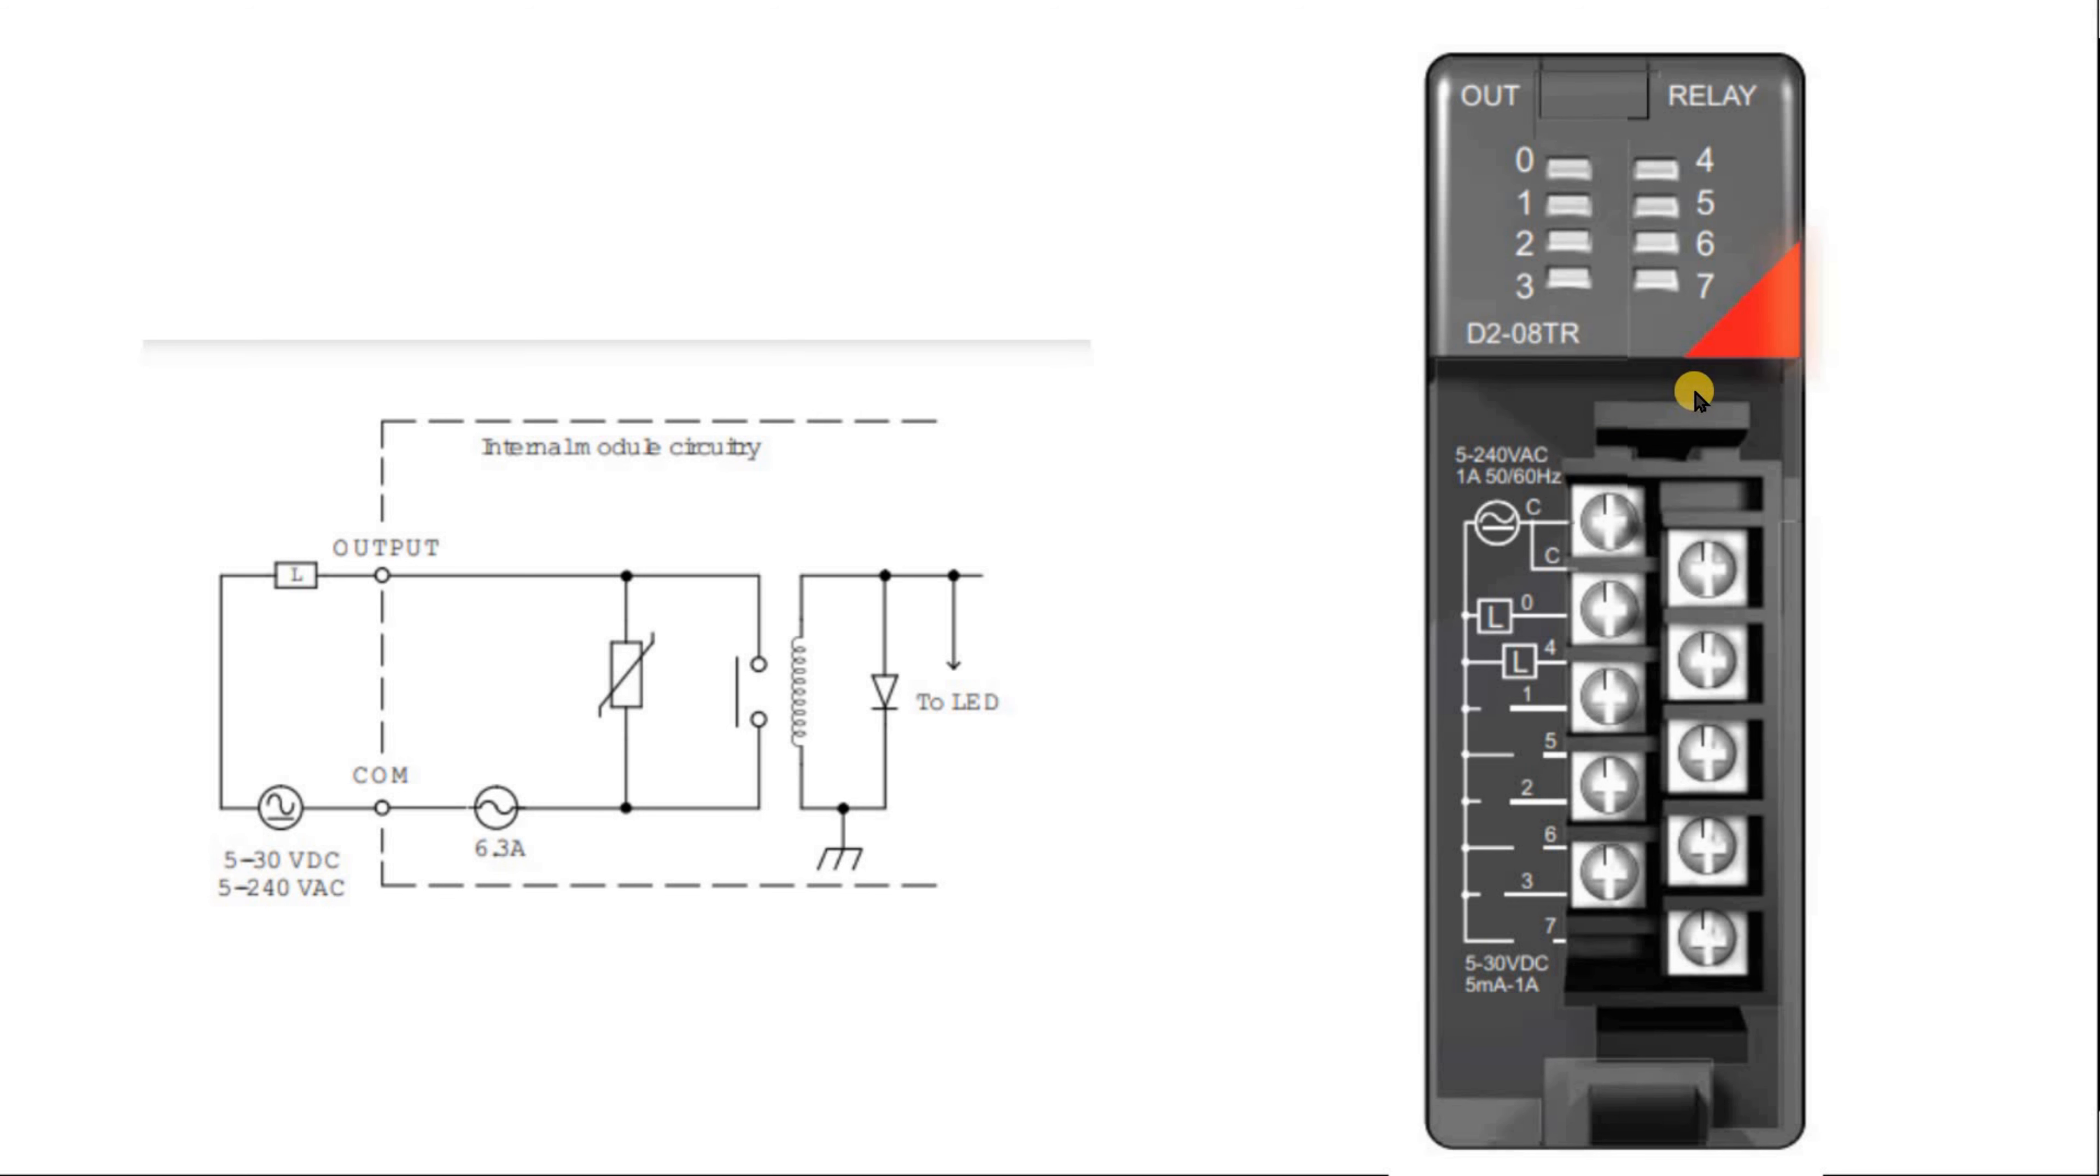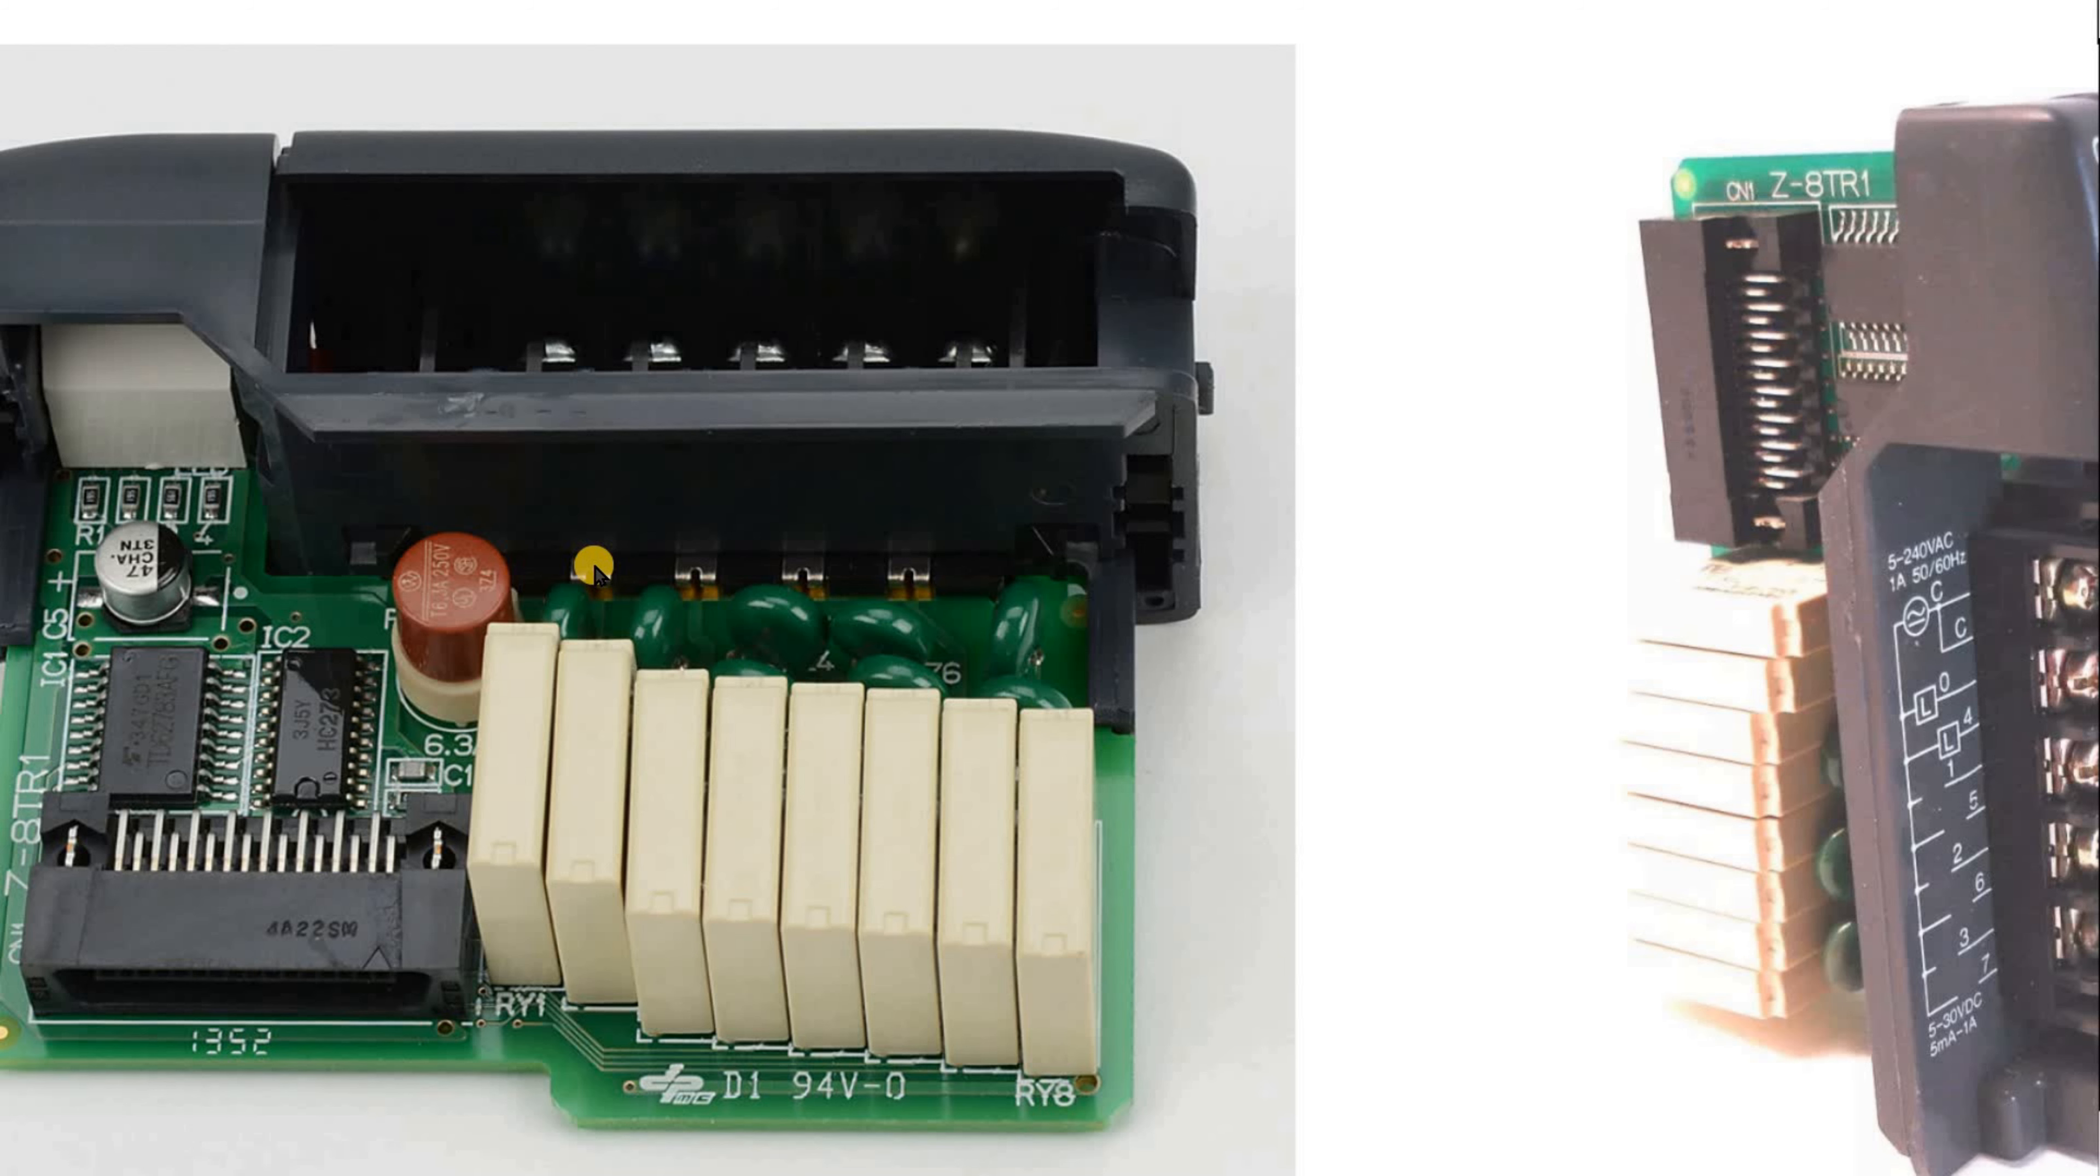The PLC is Automation Direct DL205 series. As you can see, the relay output has a fuse inside the card which should protect your circuit. Looking into the card itself, there is a fuse on a small base. The fuse wasn't there. There was no fuse, no base.